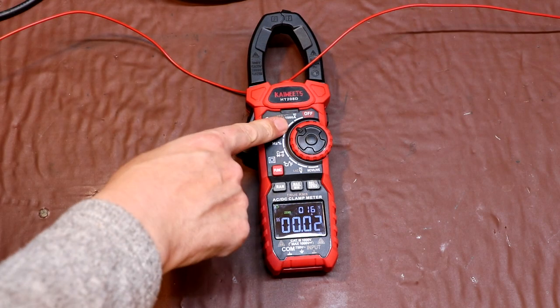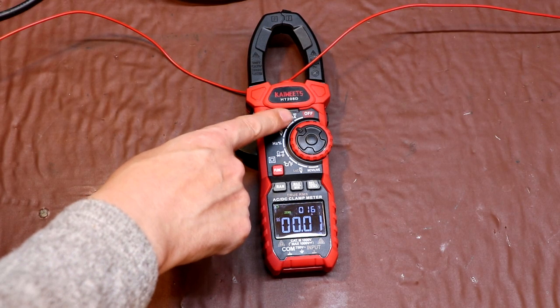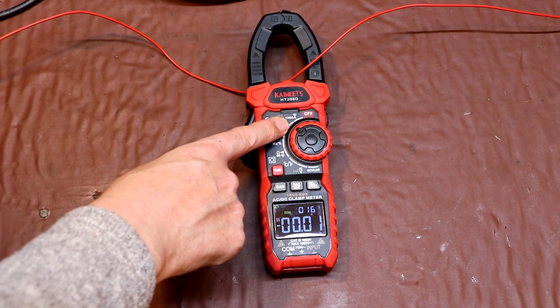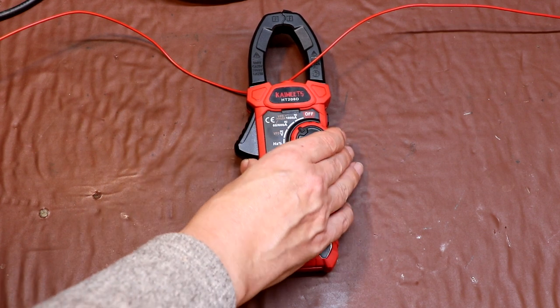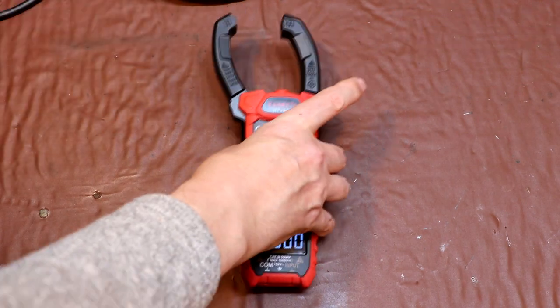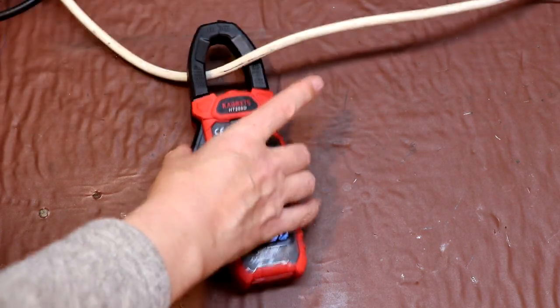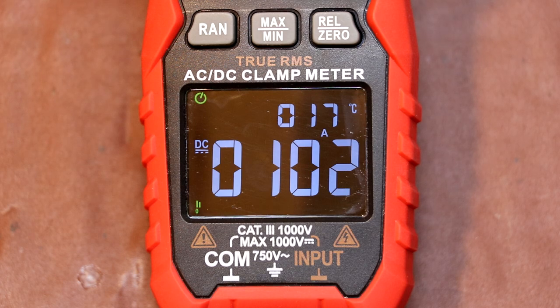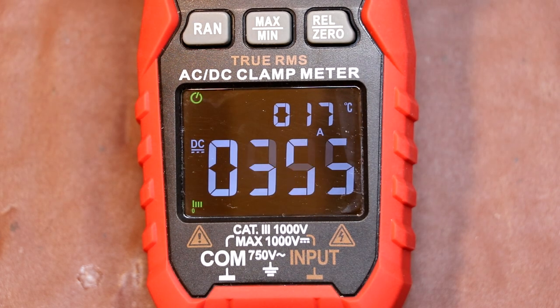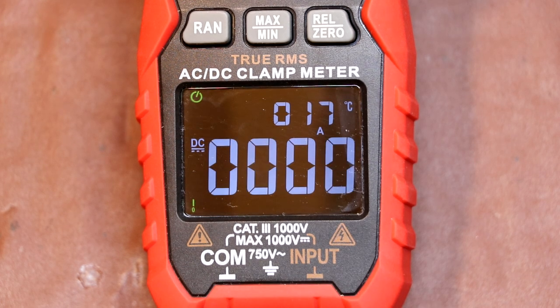The KAIWEETS meter also has a 1000 amp range. Well, it would seem rude not to test that, wouldn't it? So let's give that a go. I think we're going to need a thicker wire. At 100 amps, we're 2 counts out. At 500 amps, we're 2 counts out. I'm going to test the 1000 amp range next. The problem is everything's likely to get quite hot, smoky and melty in here, so we can only do the test very quickly.